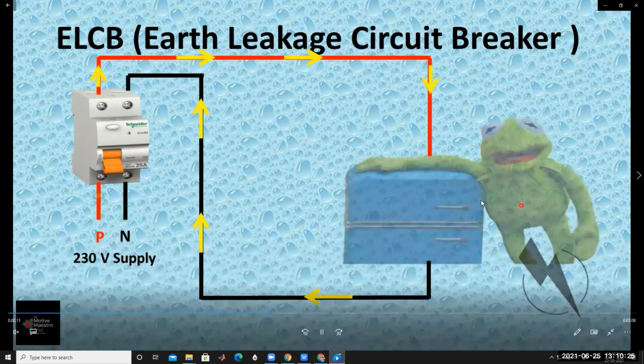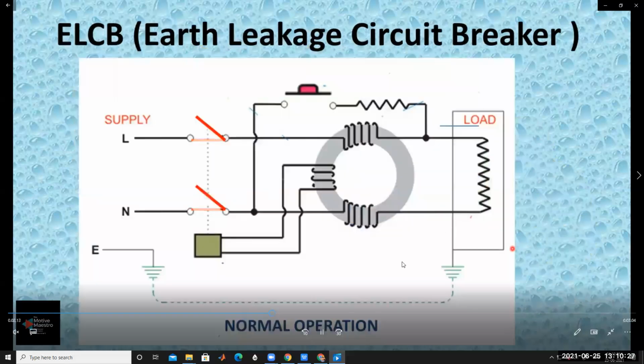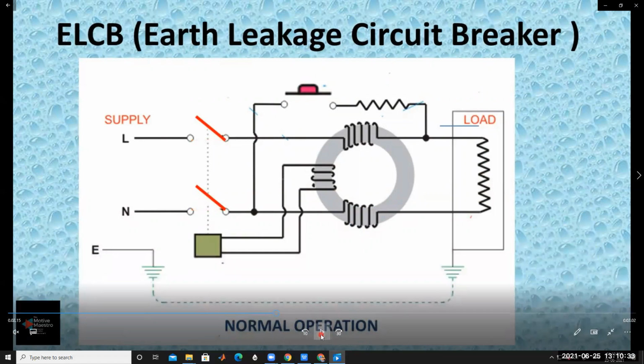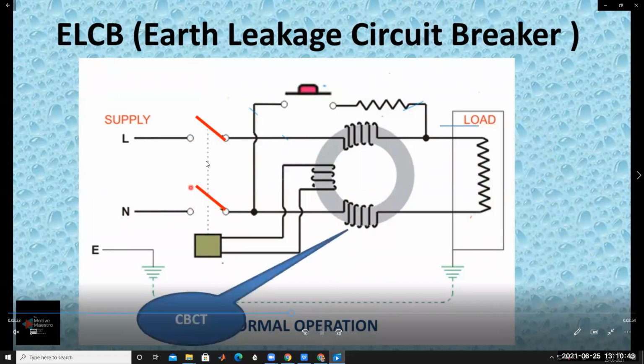Okay, so this current and this current, phase current and neutral current, are not matching. So there is a short circuit in the human body, between the phase and the ground earth. That can be protected by using an ELCB. So this is an ELCB circuit diagram. This is called the supply line and neutral. Under normal condition, it is operating. I have already explained the working principle.